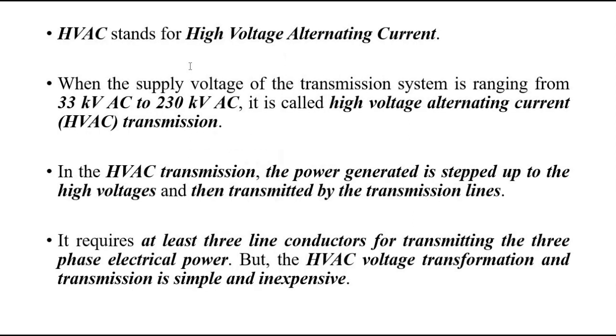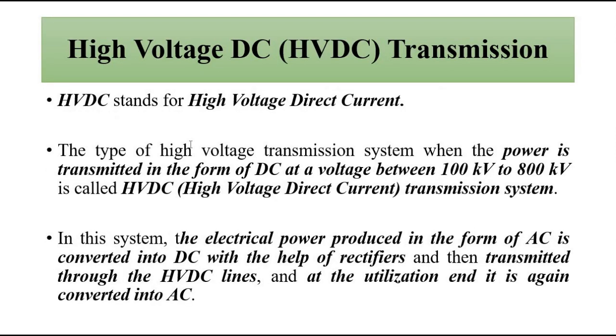In the high voltage alternating current (HVAC) system, the supply voltage of the transmission system ranges from 33 kV AC to 230 kV AC. Step-up and step-down transformers are used at different points as required — step-up transformers increase the voltage and step-down transformers decrease the voltage at particular points in the transmission and distribution network. It requires at least three line conductors for three-phase, and depending on the configuration (star or delta), three or four conductors can be used. HVAC voltage transformation is simple and less costly.